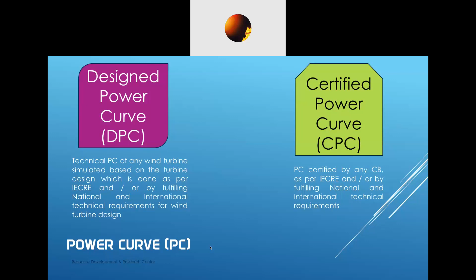Normally, it is for the certification process, where we are doing the measurement as per the standard, and the measured data is 10 minutes average data. They are corrected and normalized to the net power output for each wind speed measured at 10 minutes average with a separate meteorological mast, and then using this data and the well-defined measurement procedure as per the 12-1, they are deriving the table and graph. These two are presented. We will be seeing how it looks and everything. So these power curves are called measured power curves.